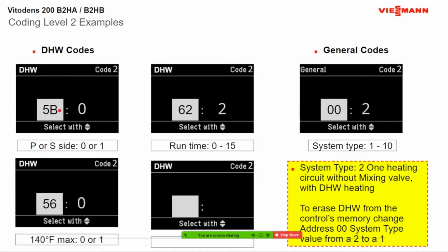Again, as I was talking about, remember, we skipped by general, we went by boiler, now we're at DHW programming. Here's that 5B I've been talking about, primary side or secondary side. So you go to that 5B and it's set for the primary side. If you're on the other side of your low loss header, you'd go here, hit OK until 0 is highlighted, hit your up arrow, put the 1 in there, and then you're good to go. It will operate correctly.